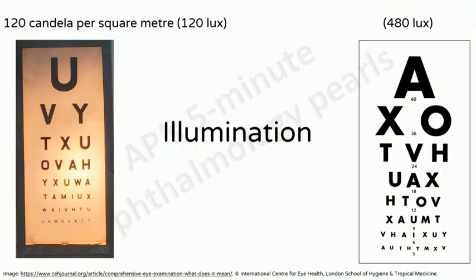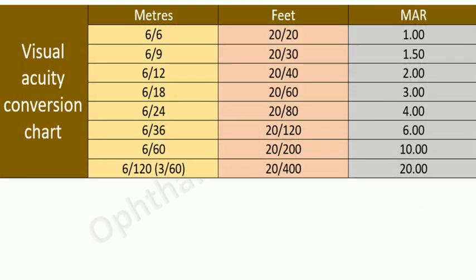Since the degree of illumination can influence the acuity, an internally illuminated chart should have a minimum background illuminance of 120 candela per square meter or 120 lux and an externally illuminated chart should have a minimum luminance of 480 lux. Newly installed systems should have higher illuminations to allow for diminished illumination due to aging.